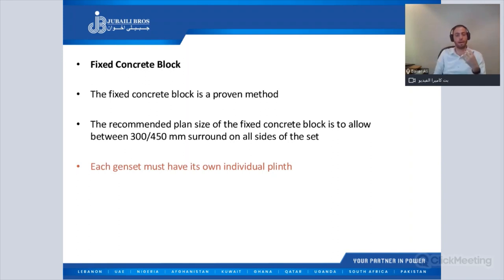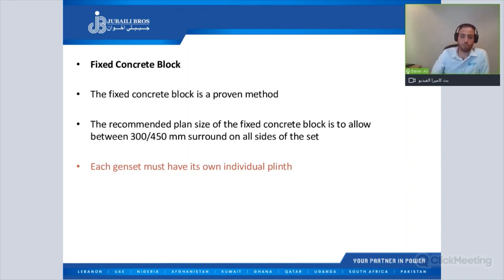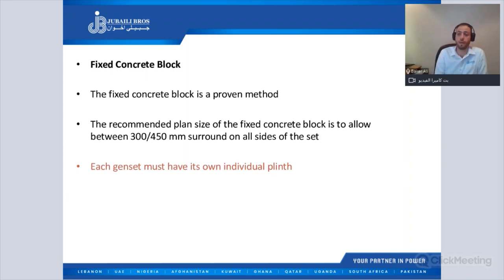Now we'll talk about the fixed concrete foundation under the generator — what is the size, including length, width, and depth. The recommended size for the fixed concrete foundation is to allow between 300 to 450 mm surrounding on all sides of the set. Each generator must have its own concrete foundation, so if you have two or three generators inside the room, you have to keep a separate foundation for each generator set.